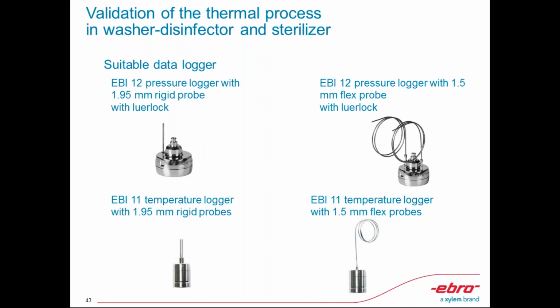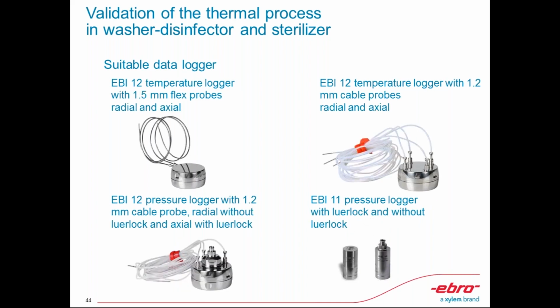So to end this webinar session, we have all the solutions for all that we have talked about in the succeeding slides. We have the most suitable data loggers for this application, for the washer and disinfection, and also for sterilization, and actually the most practical configuration. Instead of buying 4 loggers for one measuring point to be placed and fixed in their correct locations, Ebro can provide you with only 1 logger, but with long, flexible PT1000 sensors, such as this picture on your right.